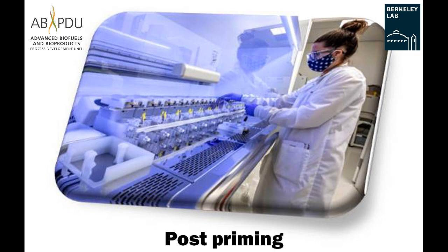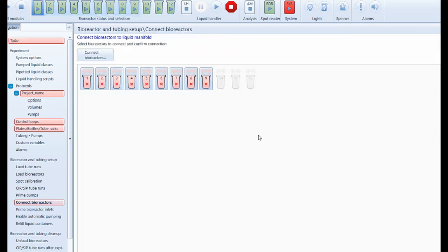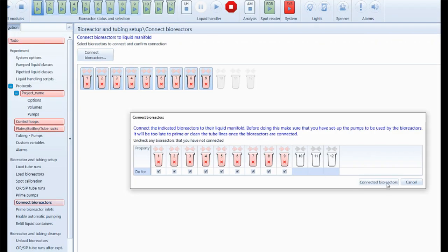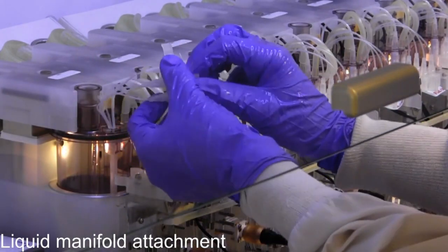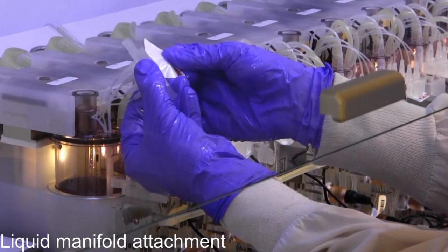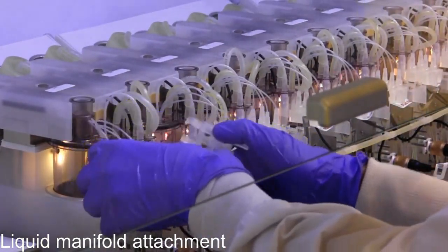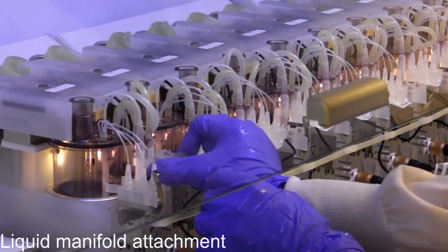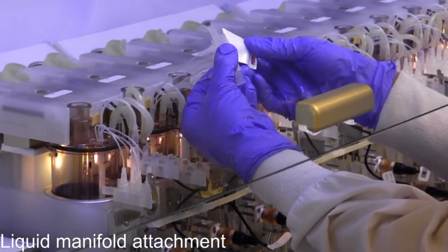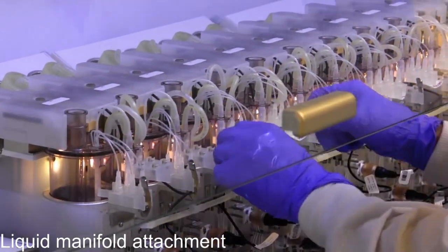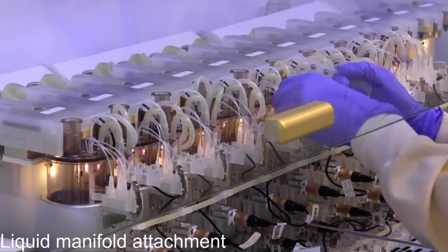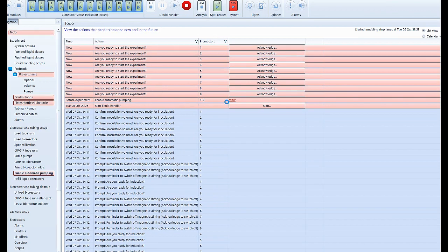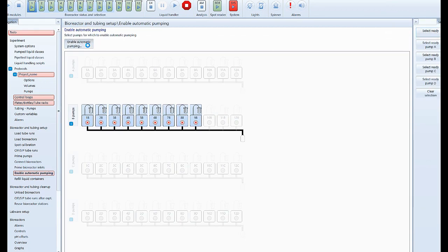Post-priming. Once priming is complete, connect the liquid manifolds to the bioreactor stations to ensure liquid can flow from the primed tube run into the bioreactor during the experiment. This is done by removing the wash cap, carefully removing the sticker on the liquid manifold, and securing it into place. To allow control loops to take over pump control, click Enable Automatic Pumping.